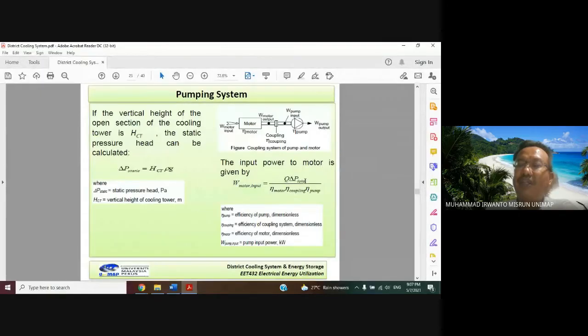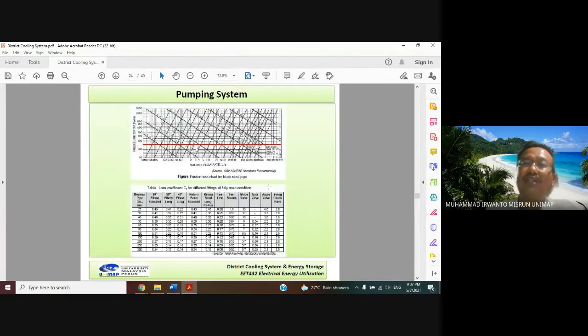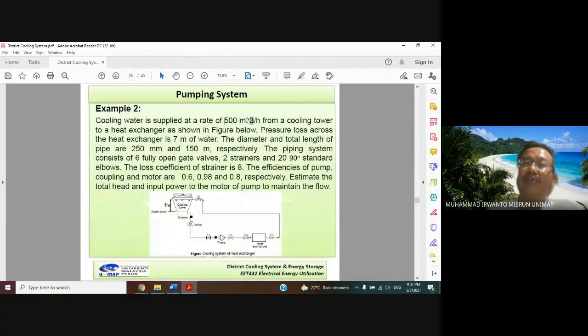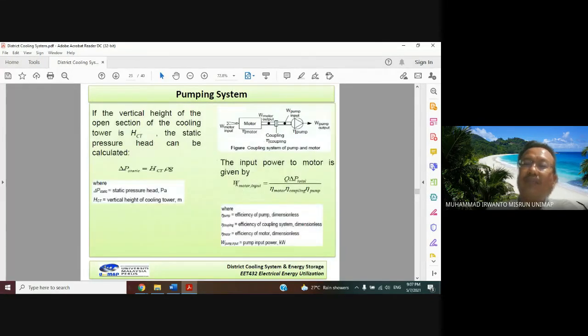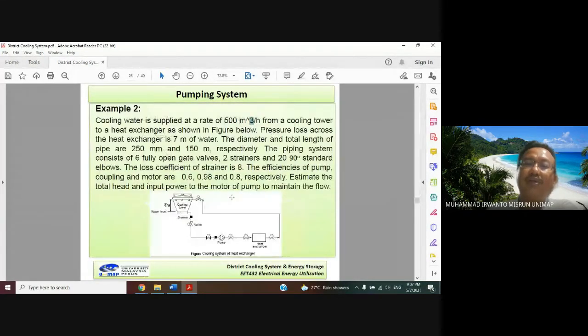After obtaining the total delta P and Q - Q here is 500 cubic meters per hour - we can convert it to cubic meters per second and liters per second. After that we can calculate the input power of the motor.